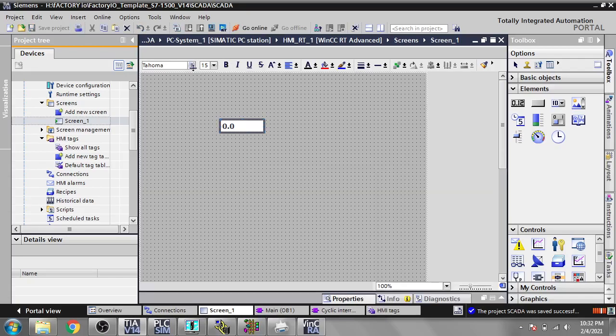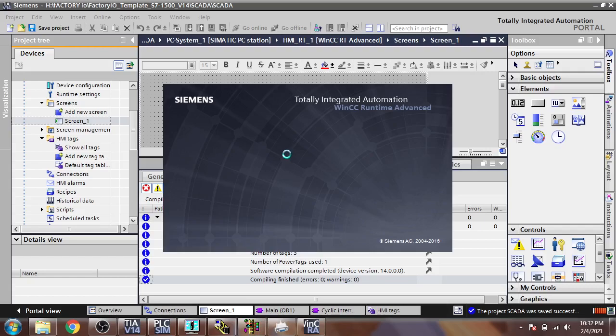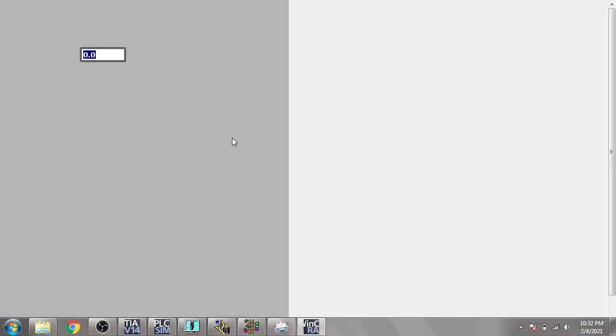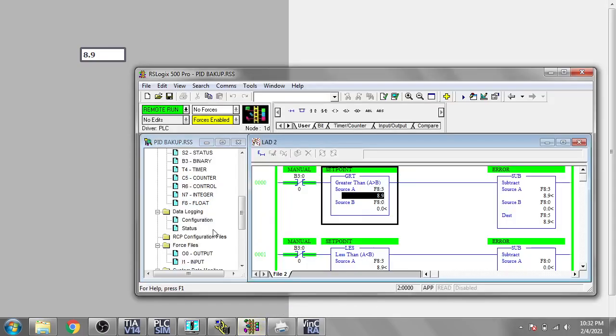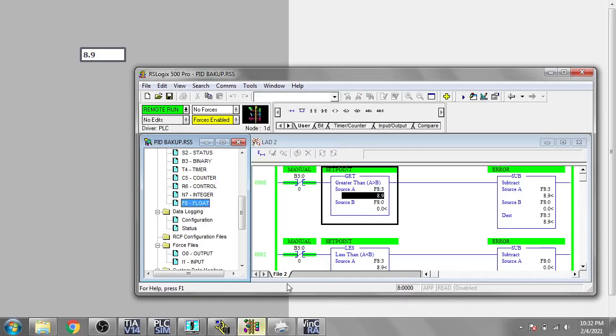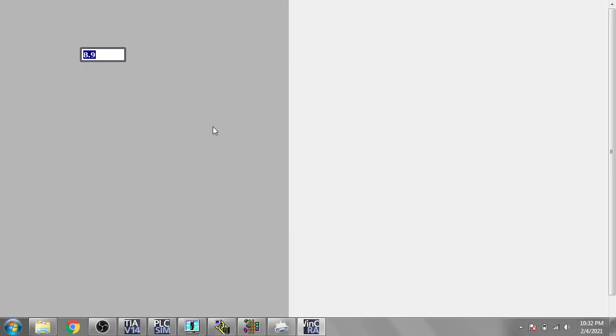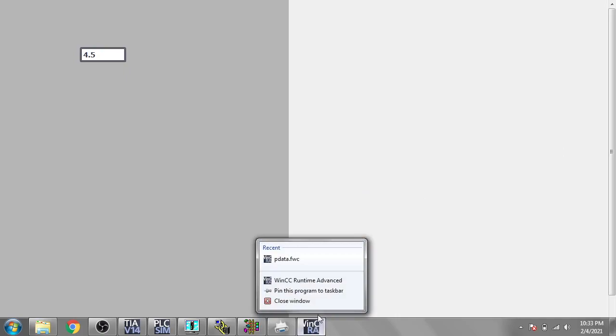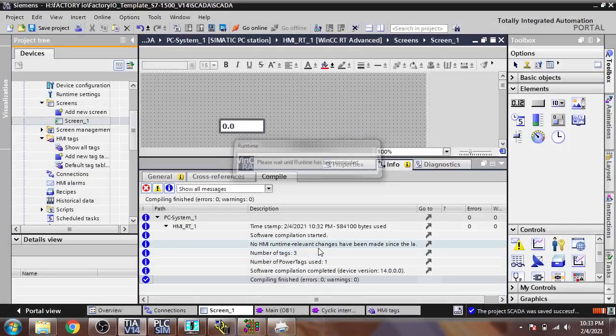I am going to compile and switch to my runtime screen. Now I am going to change the tag value — I will enter 8.9. In MicroLogix you can see it also shows 8.9, so it is successfully connected to the MicroLogix RSLogix 500 emulator. I will change it to 4.5 and you will see it updates to 4.5 in RSLogix 500 as well — it is now connected.